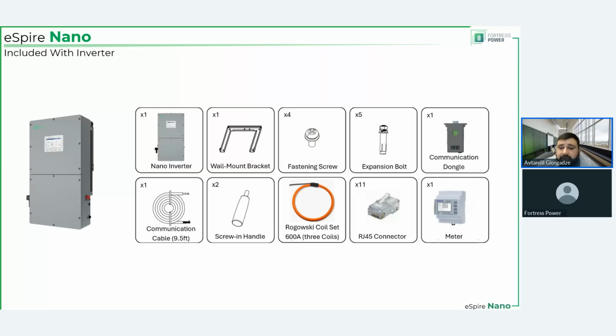But the meter to inverter communication, that can be up to like 300 feet. So that's no problem. So if you have this situation where you have the electrical panel or main panel board, or the meter for that matter, far away from the inverter, the way to go is that you have the meter and CTs close together, and then a long communication cable going from the meter to the inverter.